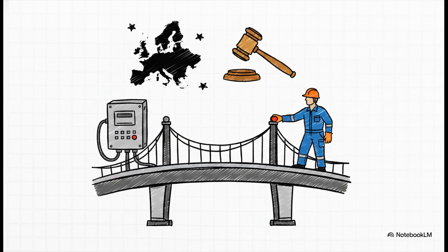European geography adds a whole other set of mandatory regulations into our mix. If your offshore unit trades in Europe or is stationed in European waters, the ATEX directives come into full effect. Now, ATEX is unique because it's statutory, meaning it's literally written into European law. Directive 2014/34/EU governs the equipment itself, making sure it won't be an ignition source. But just as importantly, Directive 1999/92/EC dictates exactly how your workers are allowed to handle and operate that equipment in explosive atmospheres. It perfectly bridges the gap between hardware engineering and daily human operations.